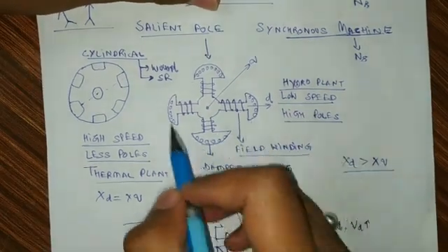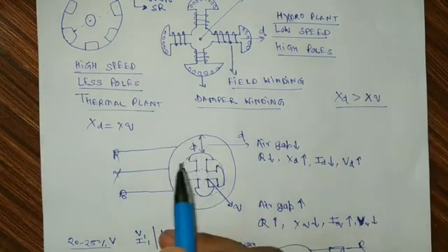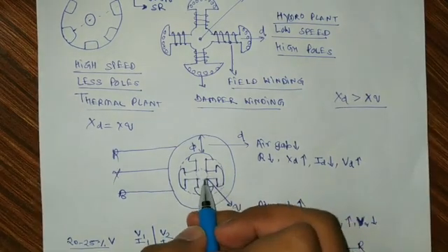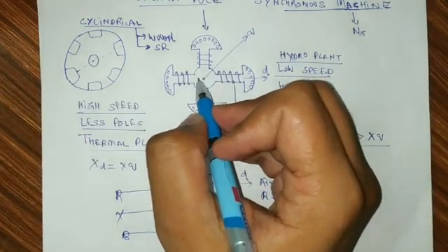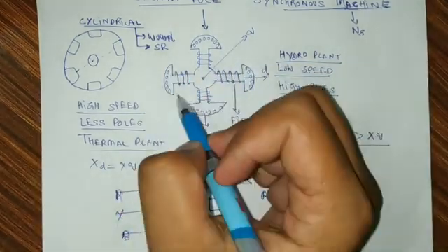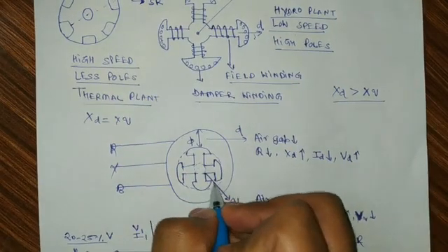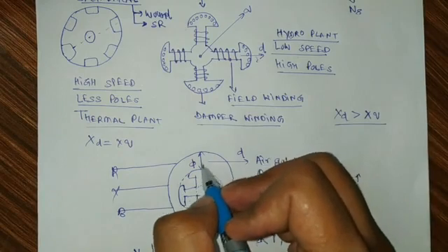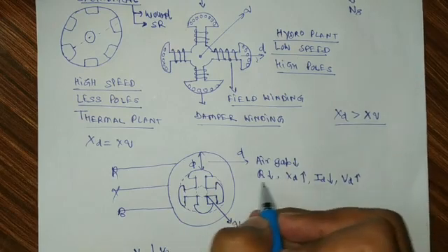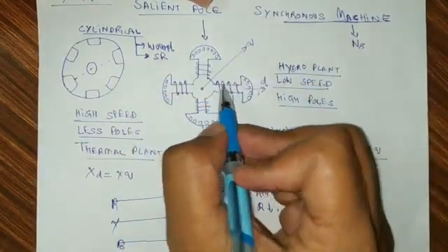Now if this type of rotor is put inside a stator with a three-phase supply, we can say this type of rotor is a combination of two rotors — one inner smaller one and one outer bigger one. The outer one will have less air gap from the stator and the inner side will have more air gap. When this type of rotor is put in a stator, the side with less air gap means reluctance is less, and reluctance is less means this side will get higher reactance. We call these axes as direct axis (d-axis).